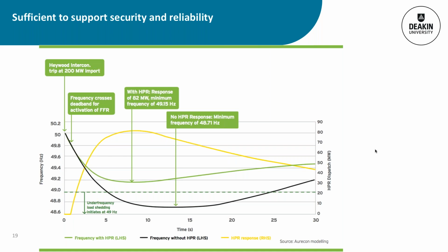This is a report done by Aurecon on the performance of the battery over the last year. The Heywood interconnector—the interconnection point between Victoria and South Australia—tripped, losing 200 megawatts instantaneously. The frequency started to fall, and on the chart, the bottom scale is seconds: well within 5 seconds, in fact within about 1 second, the Hornsdale battery, HPR, activated.